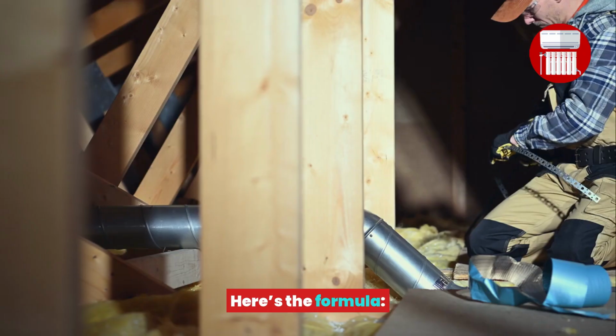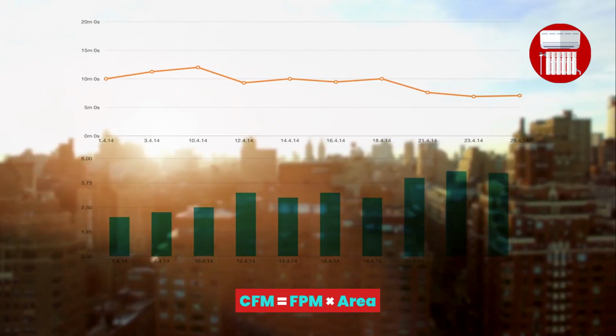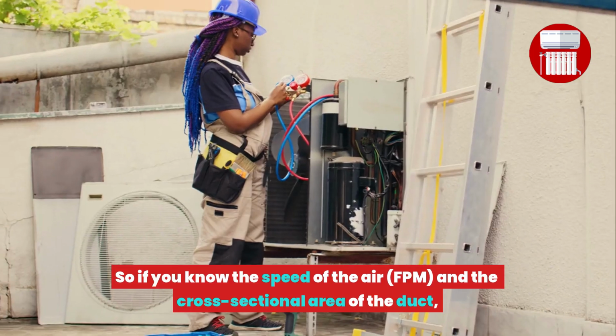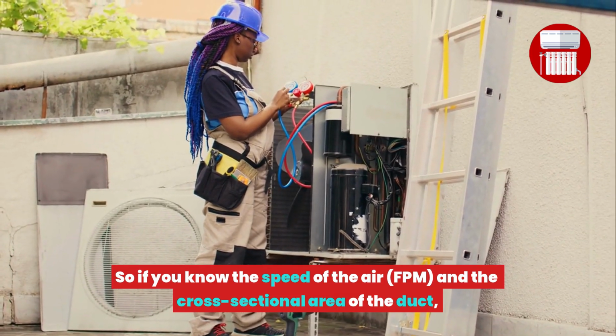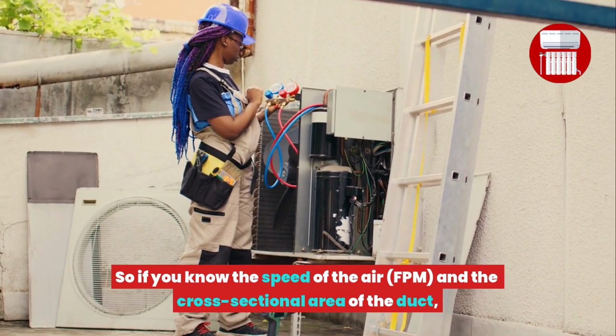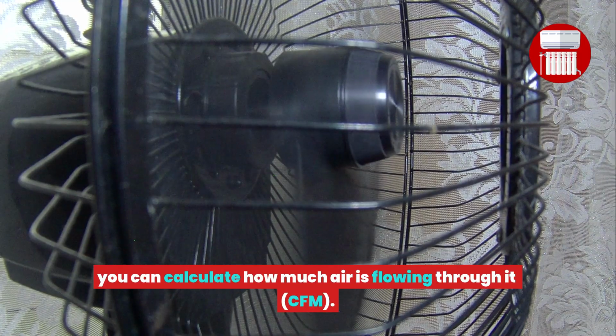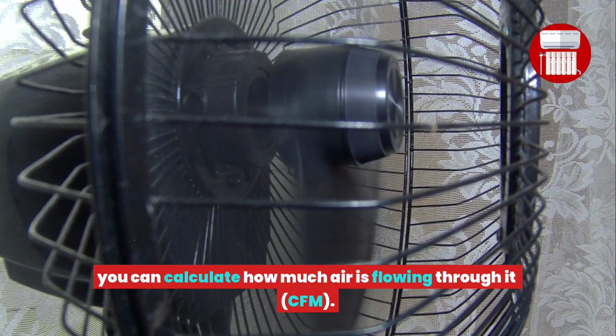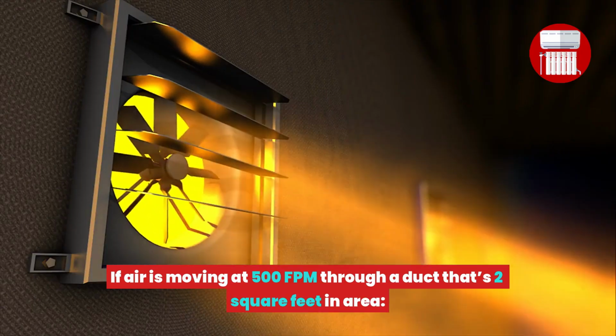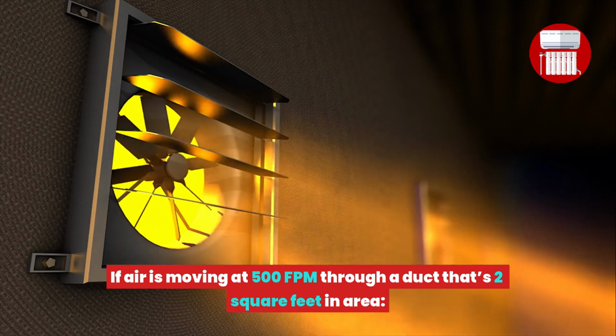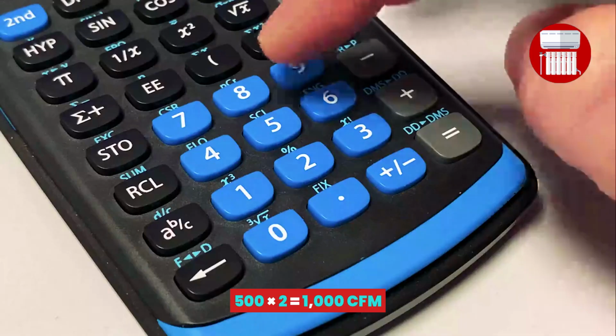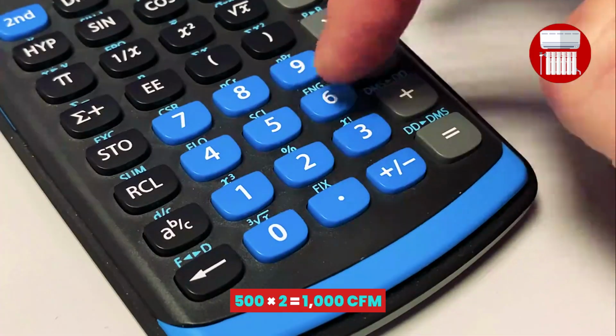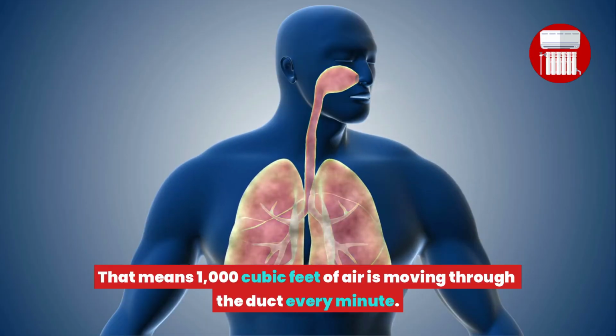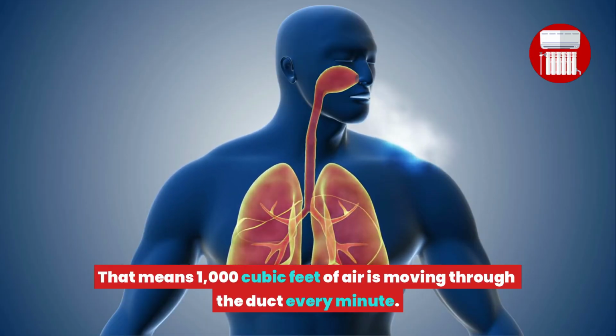How they're connected, here's the formula: CFM = FPM x area. So if you know the speed of the air, FPM, and the cross-sectional area of the duct, you can calculate how much air is flowing through it, CFM. Example: if air is moving at 500 FPM through a duct that's 2 square feet in area, 500 times 2 equals 1,000 CFM. That means 1,000 cubic feet of air is moving through the duct every minute.